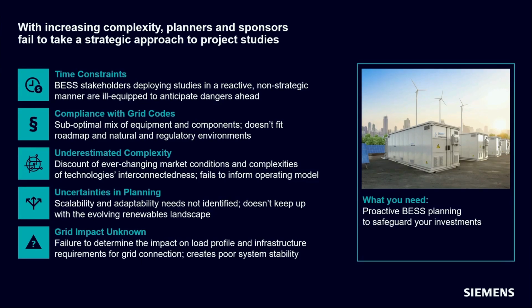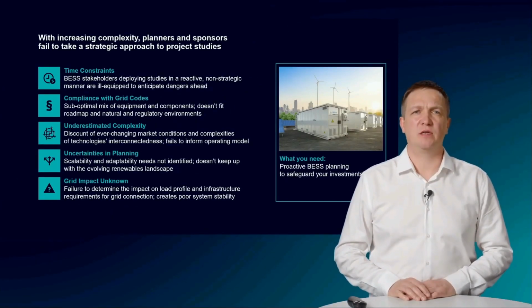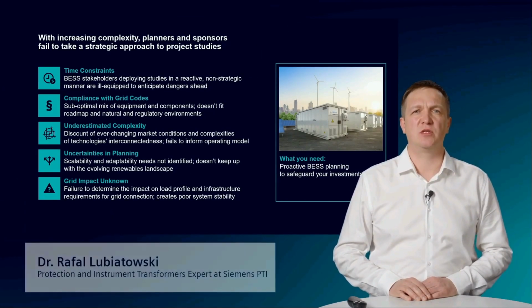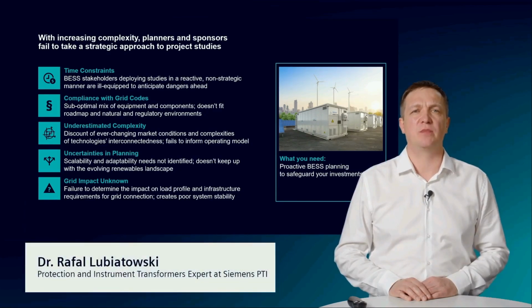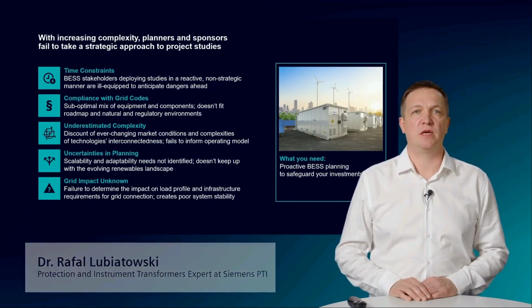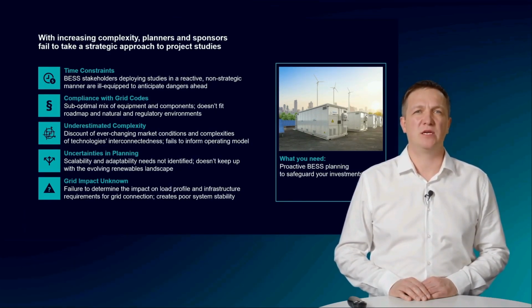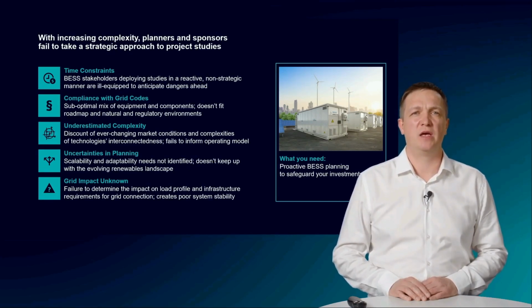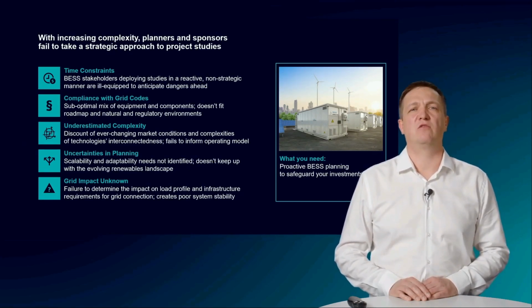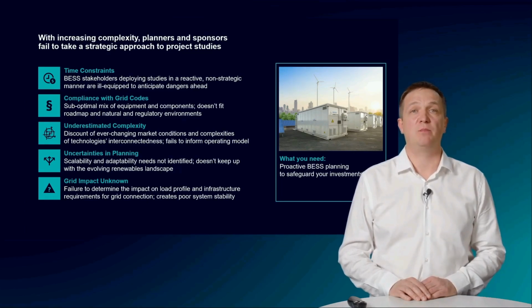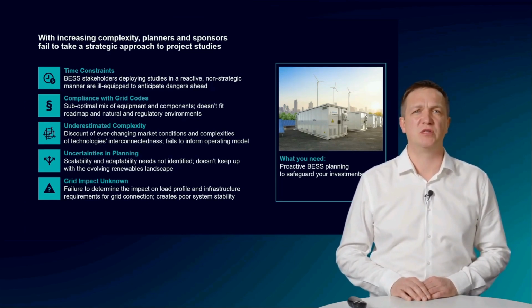Hi, my name is Rafał Lubiatowski. I am a senior consultant and a portfolio owner for protection and instrument transformers at Siemens PTI. I would like to give you some technical insights into BESS installations used as a grid booster in high-voltage transmission systems. The main aim of this kind of BESS application is to feed in power into the high-voltage transmission system within a very short period of time and stabilize it, for instance, in case of faults in the grid.